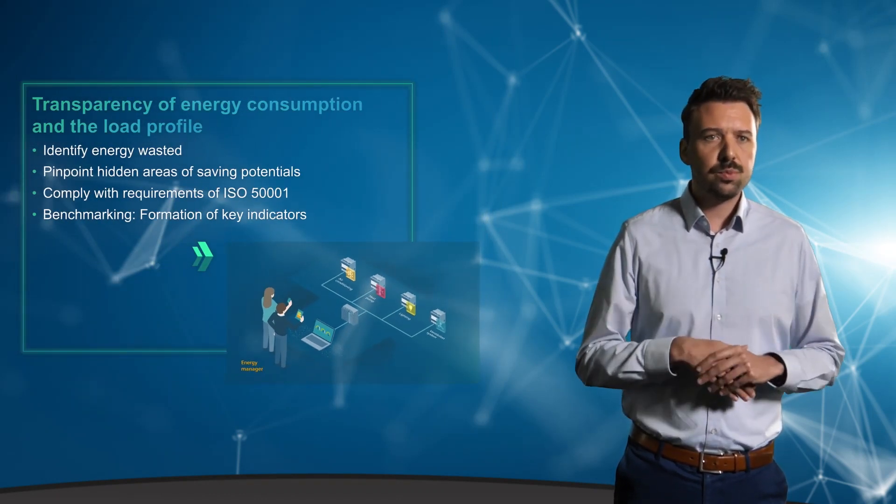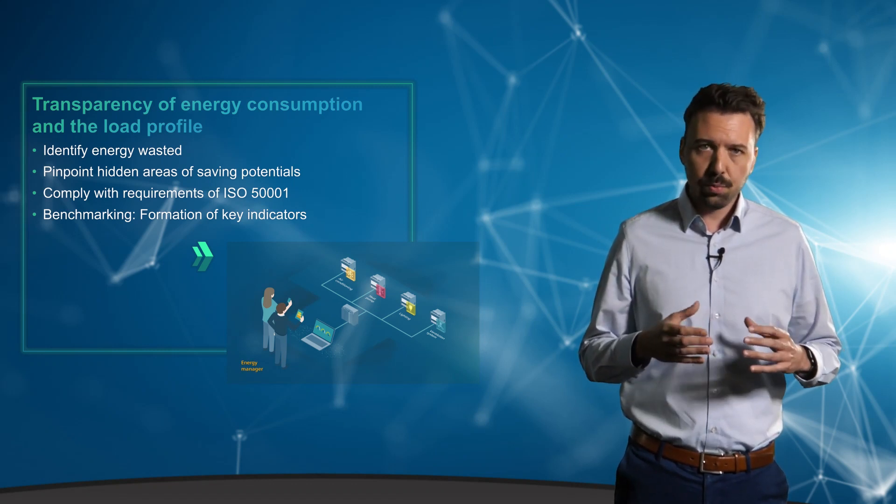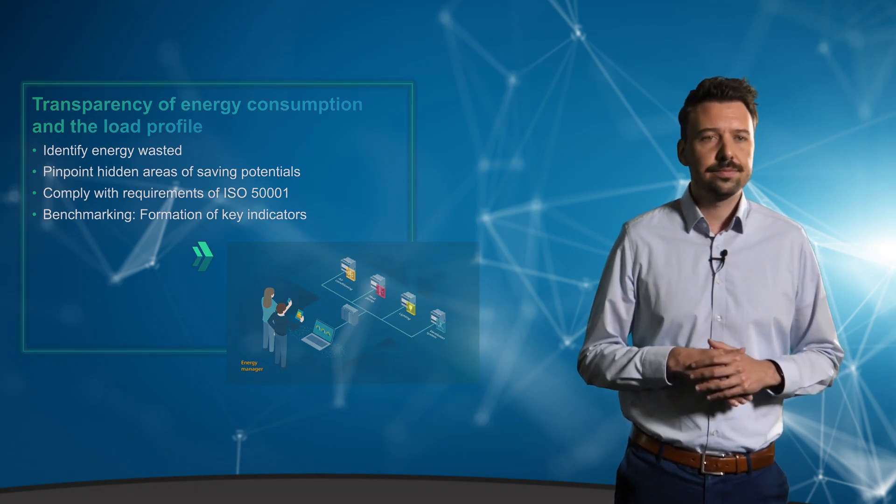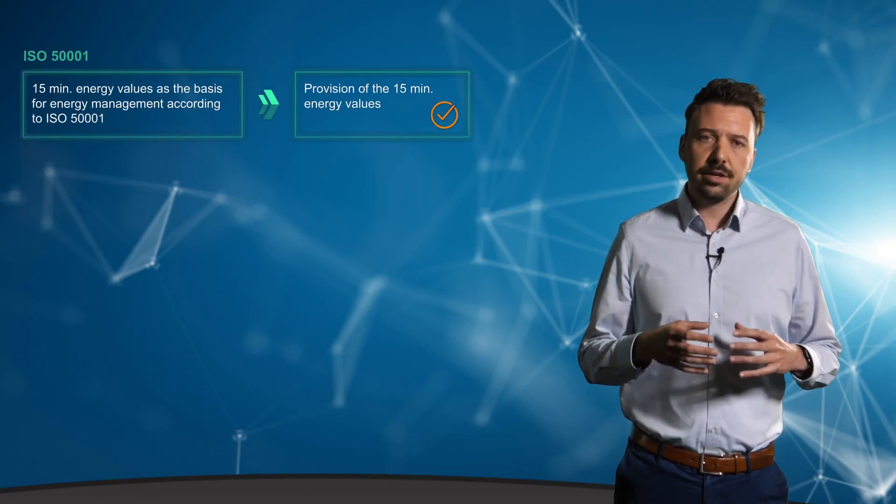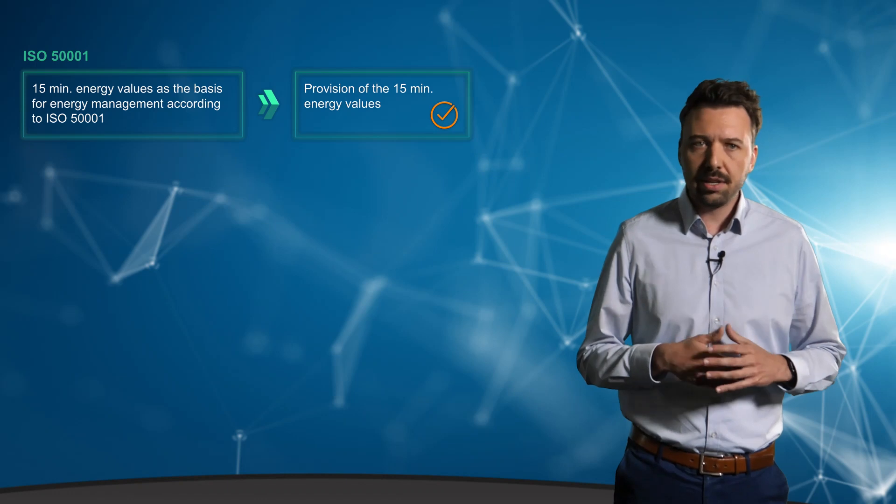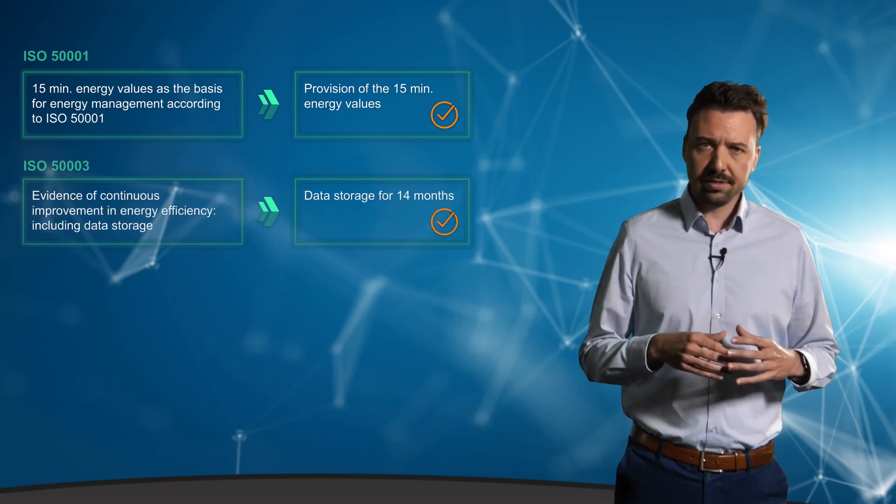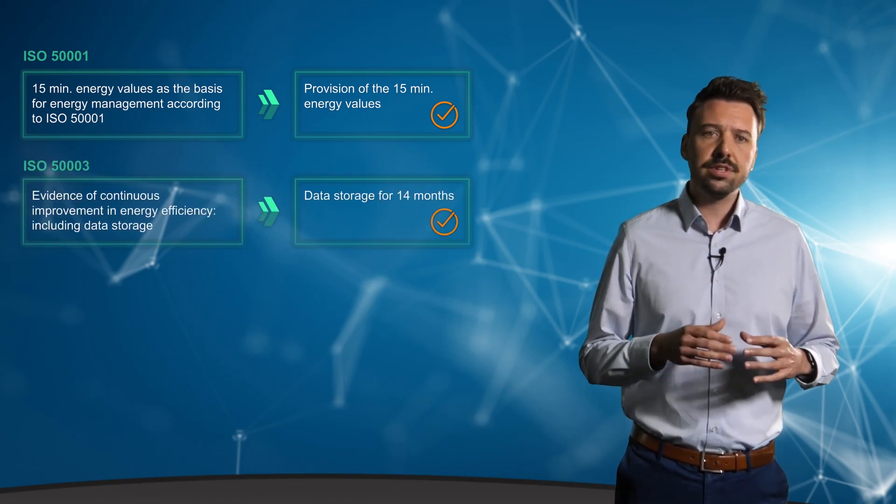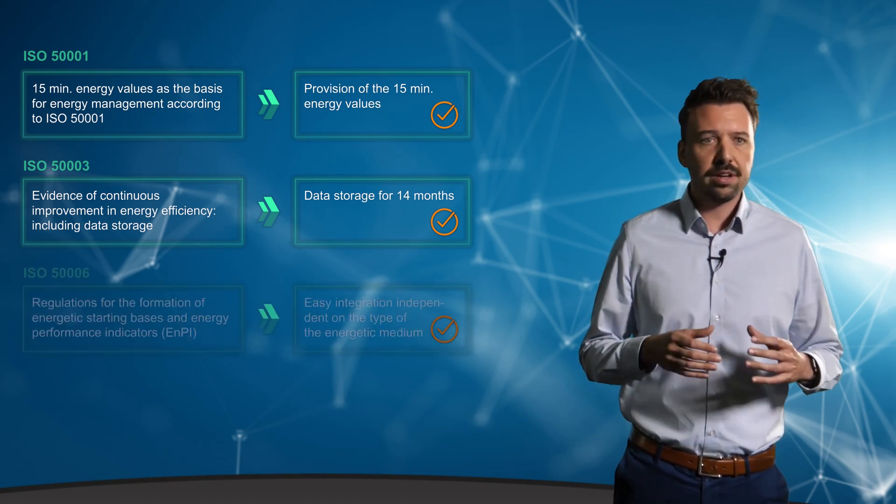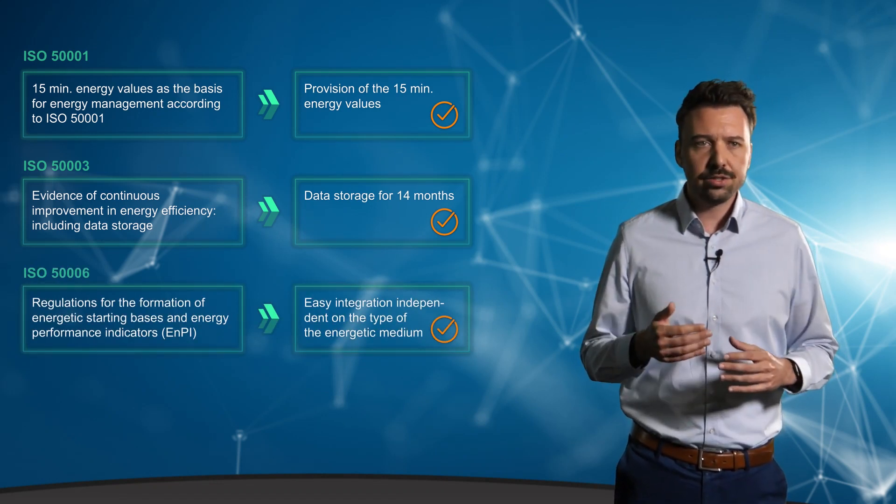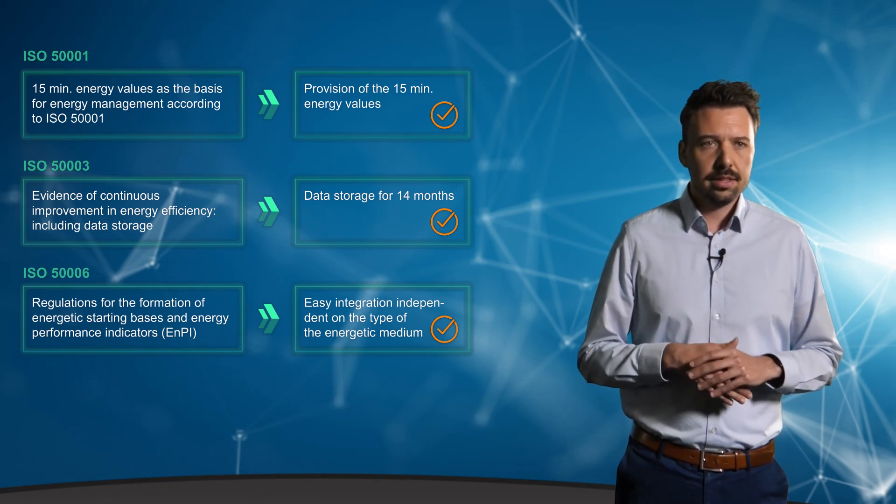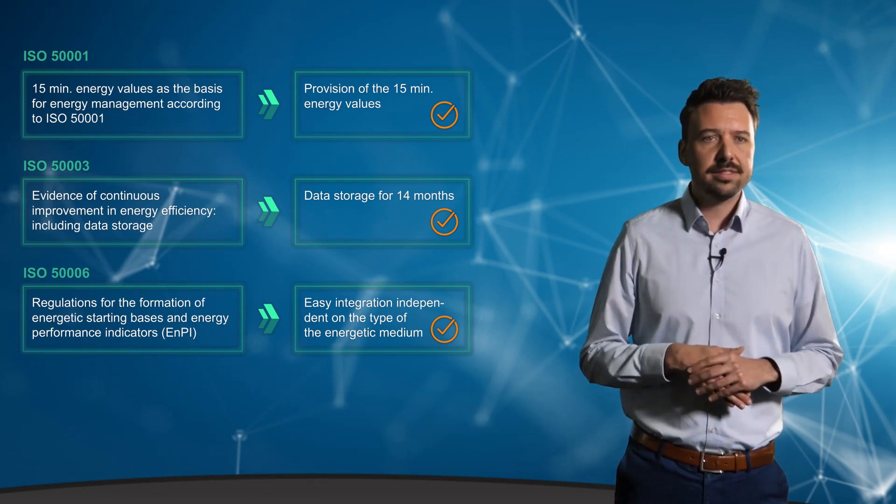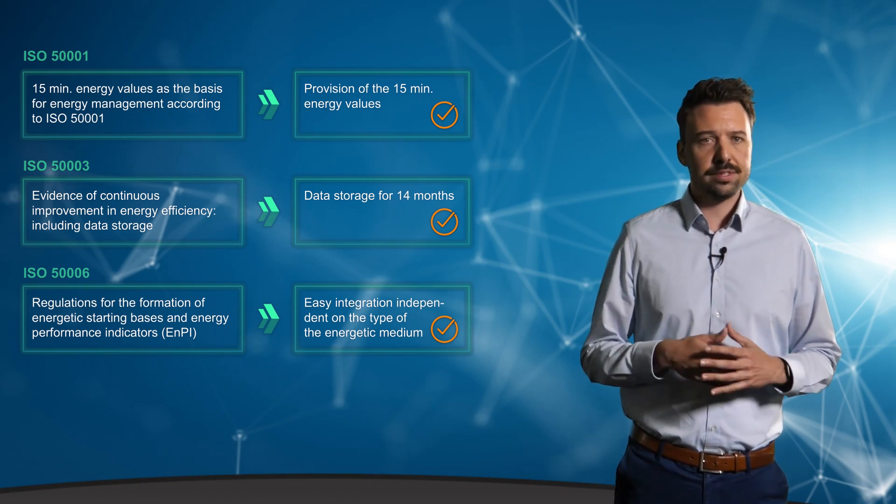ISO 50001 has certain requirements, some of which we'll take a closer look at here. There's the main ISO 50001 standard that requires 15 minutes of mean values, as well as the accompanying 50003 standard for proven continuous improvement, and last but not least the 50006 standard for recommendation of possible performance indicators. The interaction provides the basic requirements for a certified corporate energy management system.